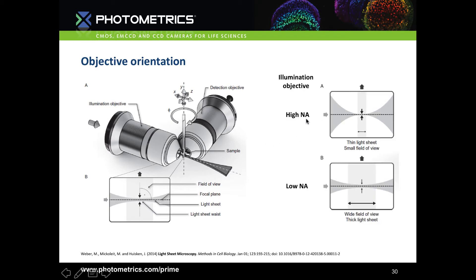The thickness of the sheet — the beam waist — is what the resolution of a lightsheet is based on: the thinner the lightsheet, the better the resolution. The field of view is dictated by the detection objective, and the aim is to match it so the field of view matches the position of the beam waist. A high NA objective gives a thin lightsheet but a small field of view; a low NA objective gives a thicker sheet but a larger field of view. The decision depends on sample size.